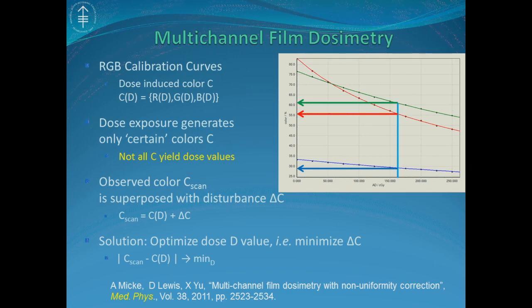range to 100 gray. For example, the single red channel dose range usually is up to 10 gray, versus triple channel 100 gray. The multi-channel method can optimize the calibration and correlate calibration parameters for best consistency. Therefore, one can significantly improve dose map accuracy. For example, 1% is achievable in triple channel versus 3% in the single channel method.